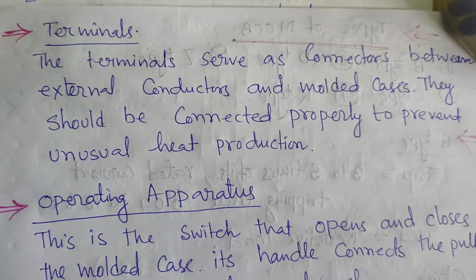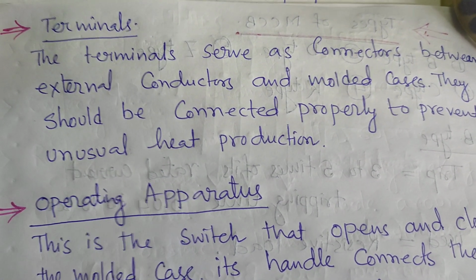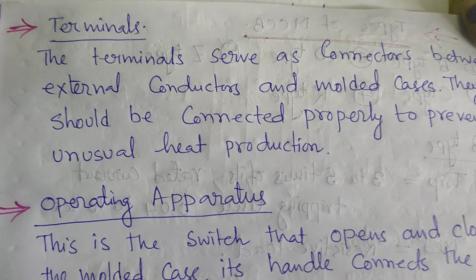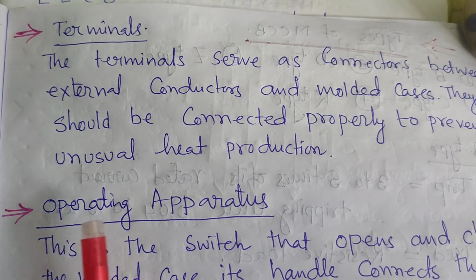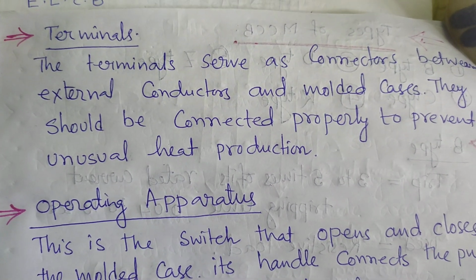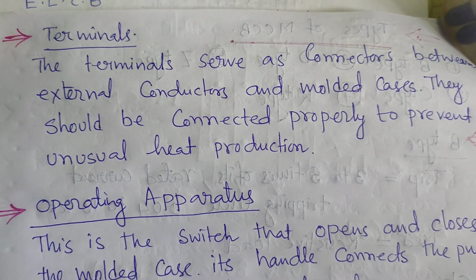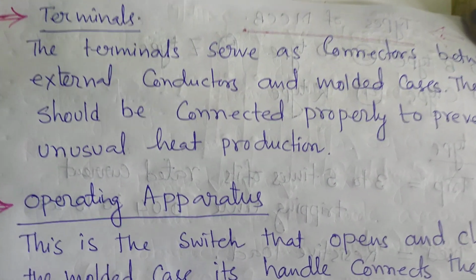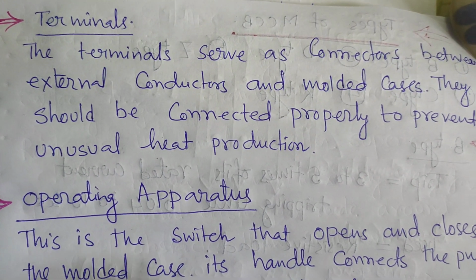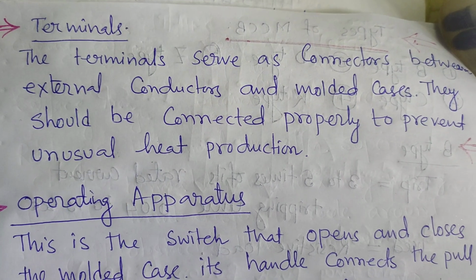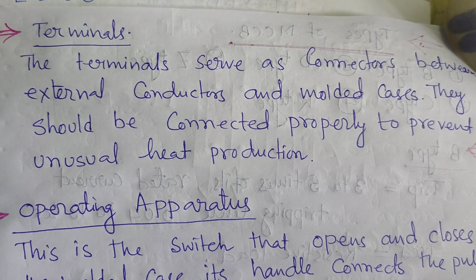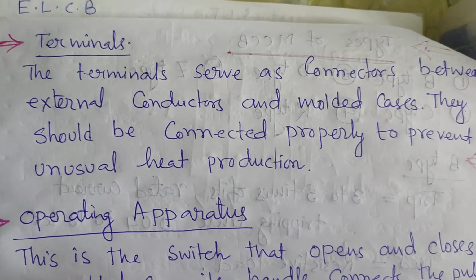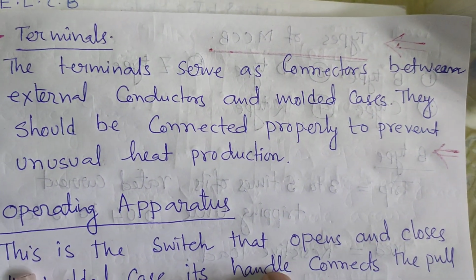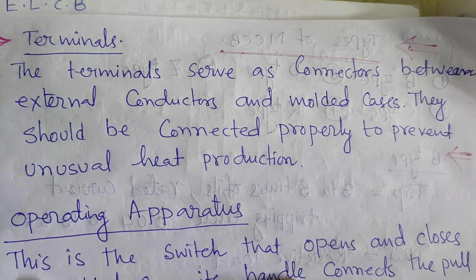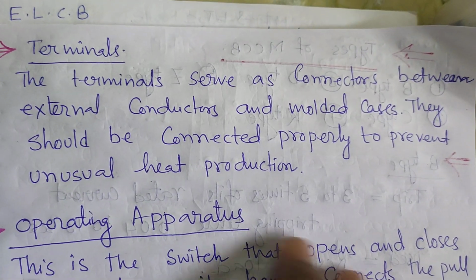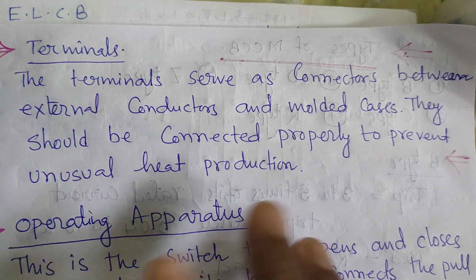Terminal serves as a connector. What is a terminal? It is where the input and output conductors or systems are connected. That is called the terminals. So it has 6 terminals, 3 on the input and 3 on the output. The terminal serves as a connector between the external conductor and the molded case. Upper the molded case, lower the molded case, and in between are the connectors. In these connections we are just connecting the output and input.